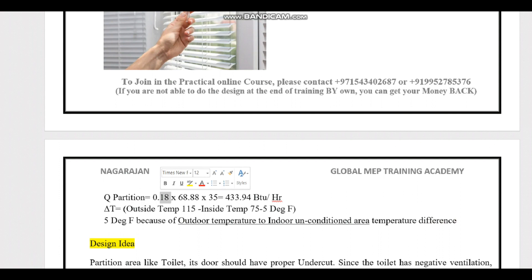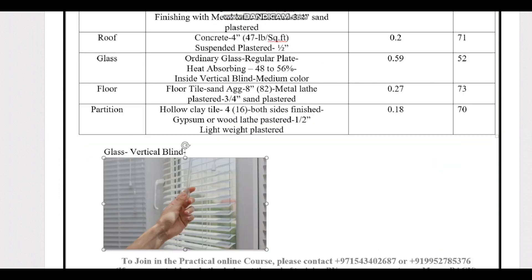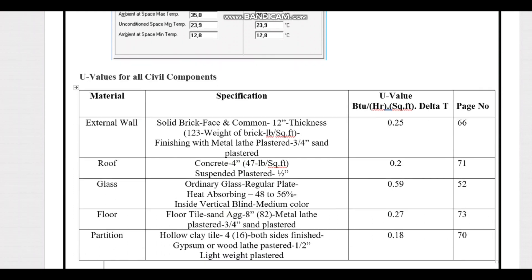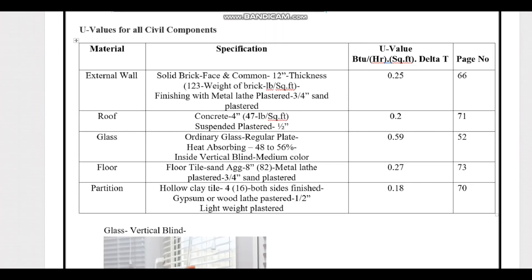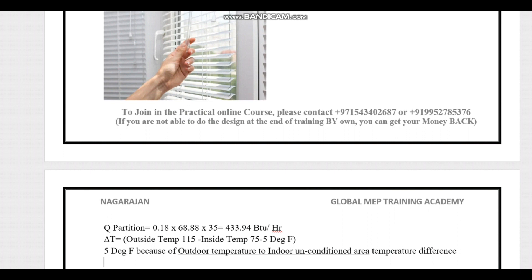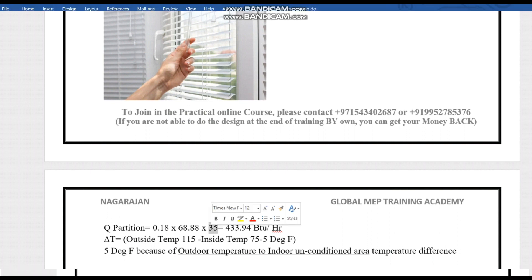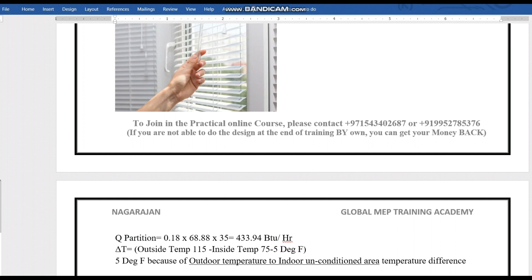Now applying the formula: Q = U × A × ΔT. The U-value for the partition is 0.18, the area is length × height = 68.88, and the Delta T — since the partition is not directly exposed to the sun and is adjacent to a non-AC area — is 115 minus 75 minus 5, giving 35°F. This gives us the Q value for the partition.